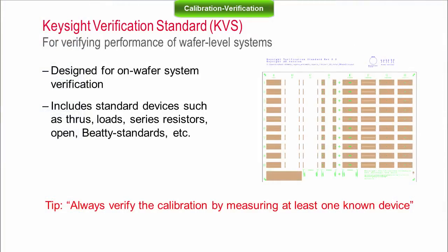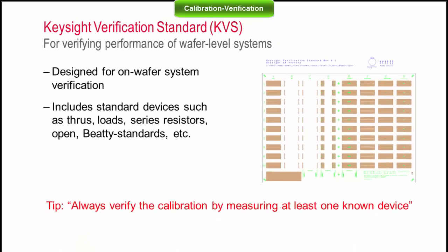At Keysight, we use a special substrate with known devices like transmission lines, Beatty standards and others to verify the newly installed systems are functional. If you can measure at least one known device and validate that its data makes sense, it will highly increase the level of confidence in your calibration.